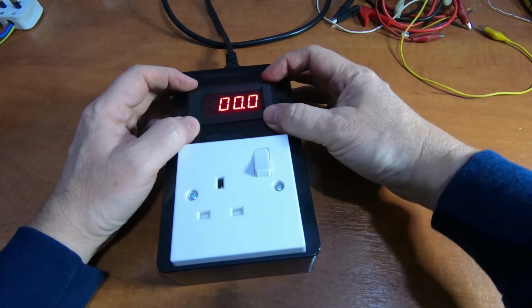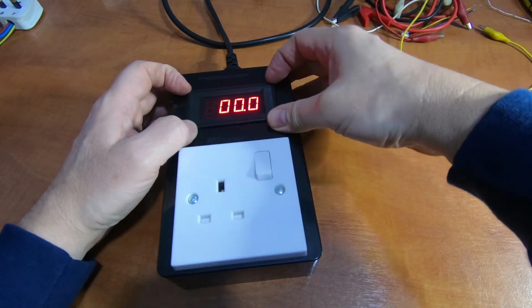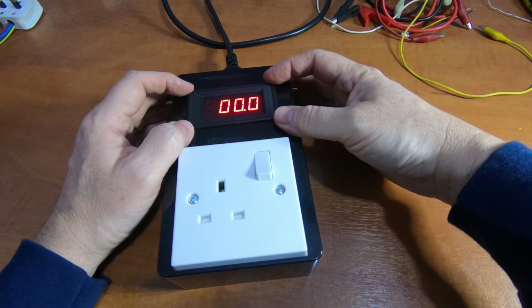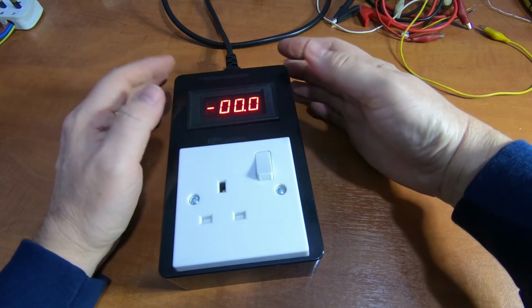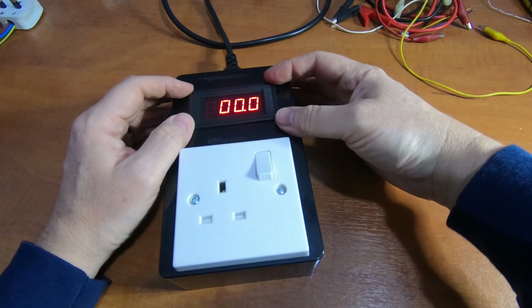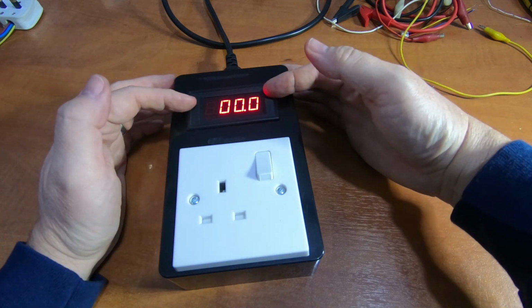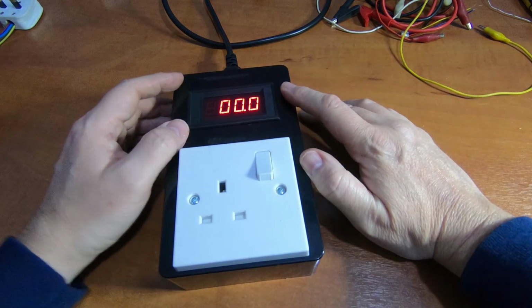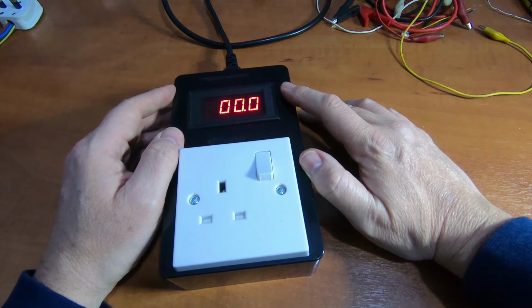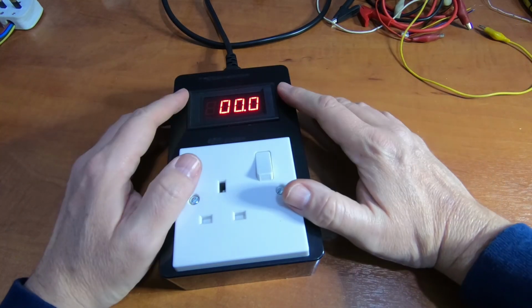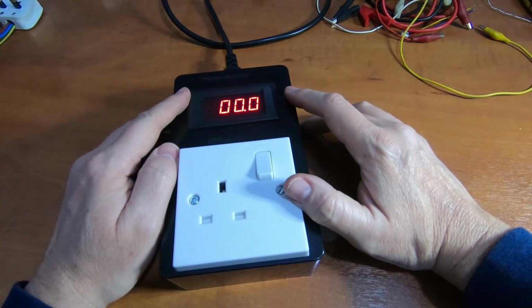If it's something over 30 milliamps, then yes, it's definitely going to trip. Or even if it's close to 30 milliamps - if this was reading 10 on a device, and you had another device reading 10 or 15, then in combination the two could be causing the trip.